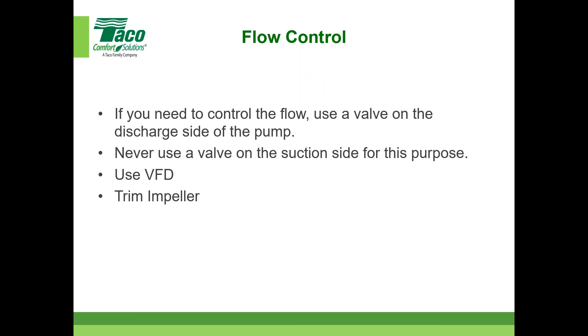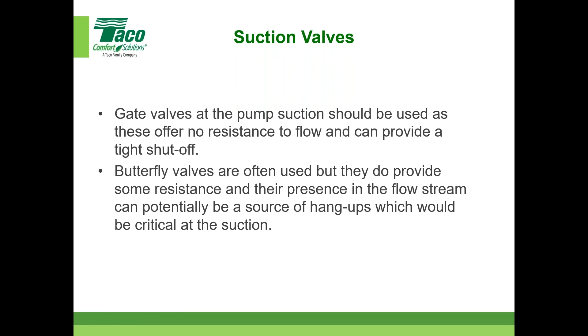We recommend using a gate valve instead of a butterfly valve. The gate valve doesn't add any resistance, while the butterfly could add resistance. If you think about the butterfly, it has a panel or wafer in there that could cause something to hang up, which would be very critical at suction. It's a small recommendation, but something to think about and discuss with others.